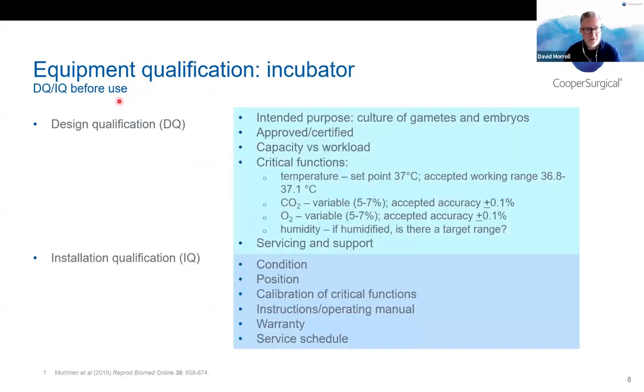So just to go into that a little bit more detail, as I said, the design qualification, and we're going to use the example of an incubator. The design qualification sets out the purpose, which is typically culture of gametes and embryos. We want it to be appropriately certified, whether that's a CE mark or an FDA approval or whichever is appropriate. We want to know that we've got the right sort of size and numbers of equipment. And of course, for incubators, we know that we'll be setting specific criteria like temperature, gas mix, humidity, and so on.